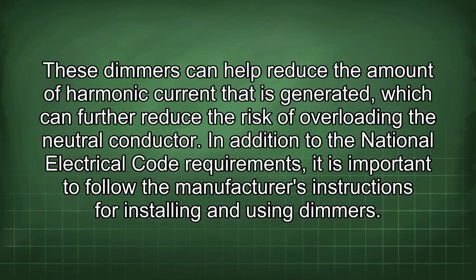These dimmers can help reduce the amount of harmonic current that is generated, which can further reduce the risk of overloading the neutral conductor. In addition to the National Electrical Code requirements, it is important to follow the manufacturer's instructions for installing and using dimmers.